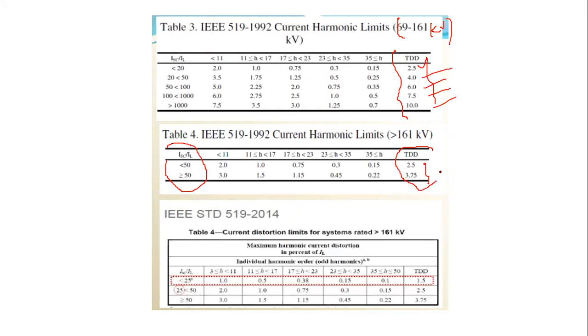Okay, now this is what was defined in 1992. Now you can see the latest 2014 version. In the 2014 version, they maximize the harmonic current distortion percentage for load current or line current. Now see this, less than 25 amperes, they convert into 20 to 25%. So they increase the levels to 20 to 25. The distortion level in those days was 2.5% THD. Now we are increasing the load current and the non-linear current also, yet the total harmonic distortion is 1.5% because we are using advanced power electronic devices to reduce this THD.